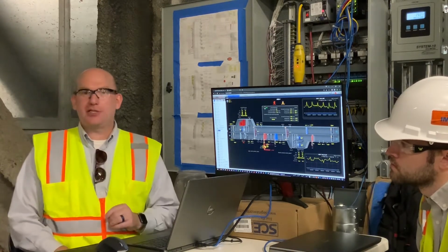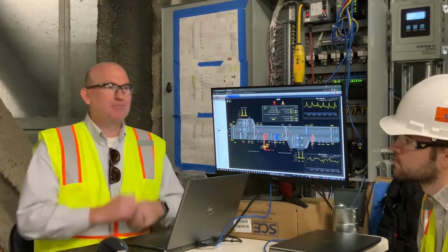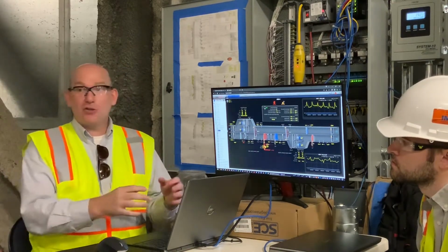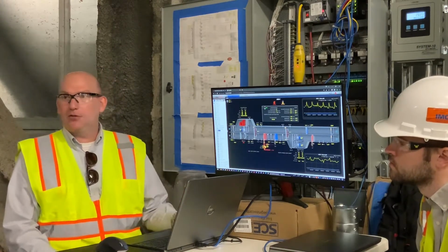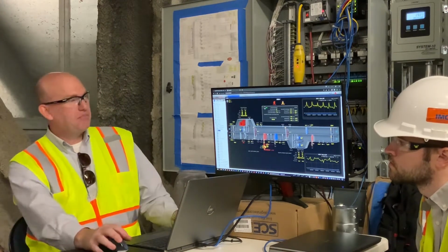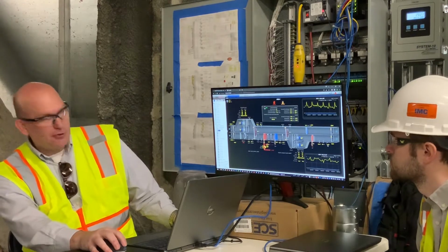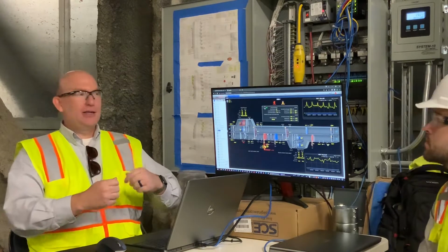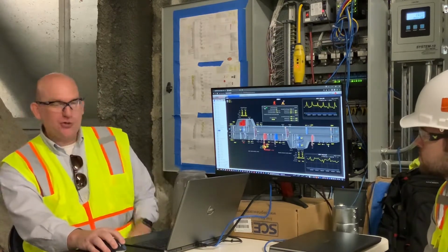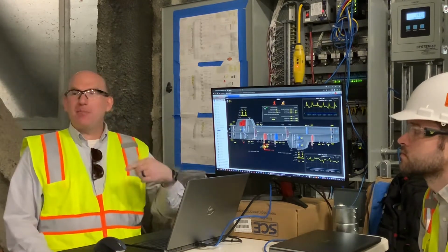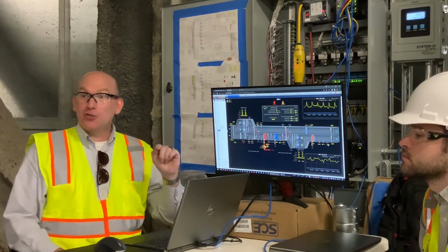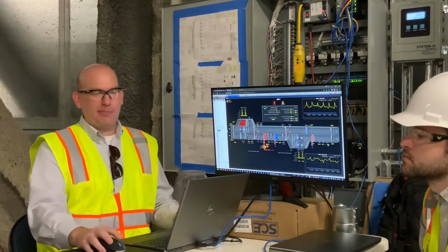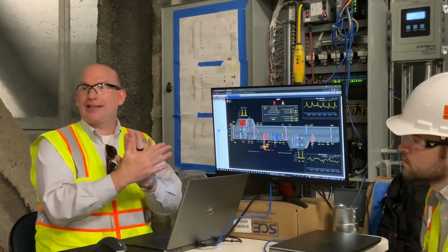If for some reason someone comes along with a Sawzall and cuts the conduit from air handler 1 to air handler 2, and air handler 1 is no longer getting that common signal, we have logic built in that looks at this pressure all the time. As the air handler is running normally, we're making 3.25. It looks at that, and every minute it records that. If it loses comm to the other air handlers, it makes that pressure its current set point and controls to the discharge at that set point.